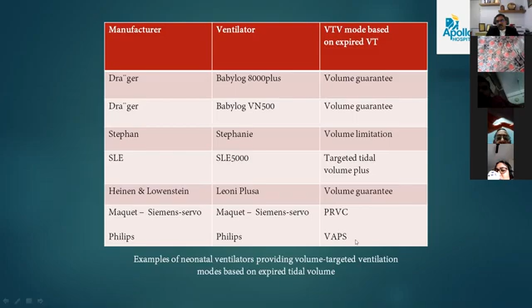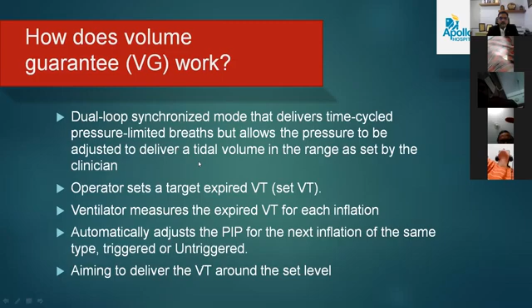So how does volume guarantee work? You set a tidal volume for the machine to deliver during every breath. How does it know how much volume to give? Every time the baby takes a breath and expires, it calculates the expired tidal volume and gets an idea how much pressure is required in the next breath to achieve the set tidal volume. There is an algorithm inbuilt in the microprocessors of these ventilators which calculates this, and so it corrects the level of pressure required. That is very well shown in this graph. Let me show you that.